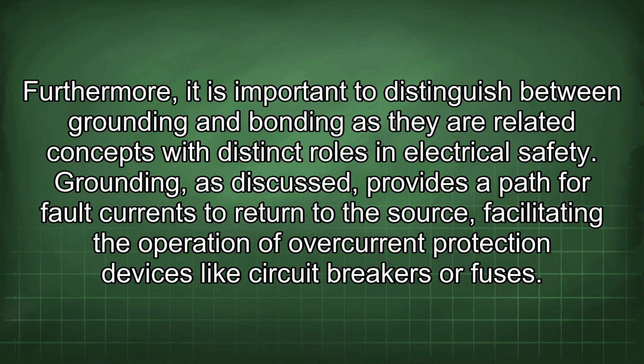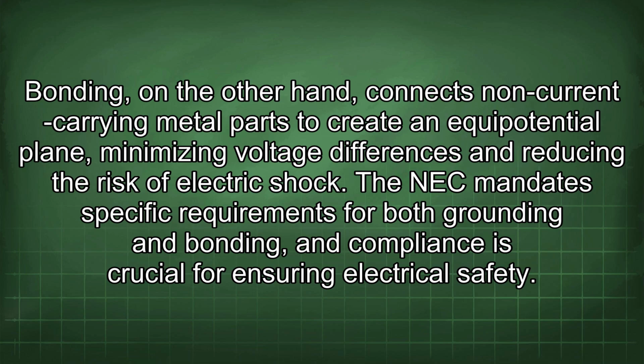Furthermore, it is important to distinguish between grounding and bonding, as they are related concepts with distinct roles in electrical safety. Grounding, as discussed, provides a path for fault currents to return to the source, facilitating the operation of overcurrent protection devices like circuit breakers or fuses. Bonding, on the other hand, connects non-current carrying metal parts to create an equipotential plane, minimizing voltage differences and reducing the risk of electric shock. The NEC mandates specific requirements for both grounding and bonding, and compliance is crucial for ensuring electrical safety.